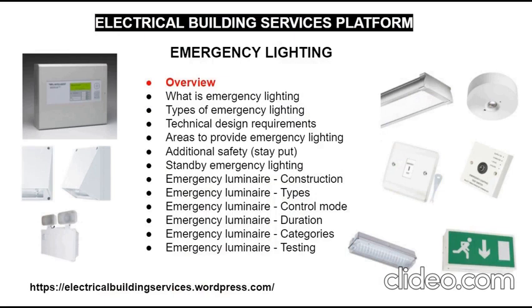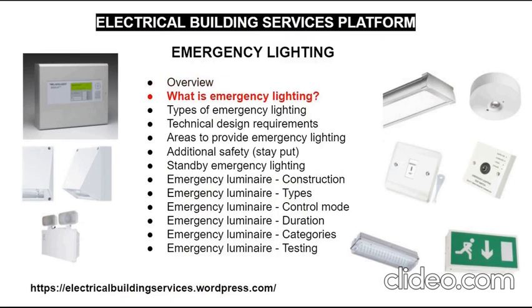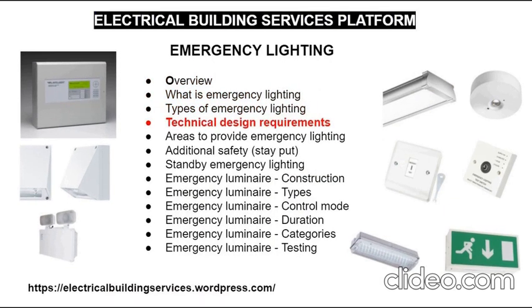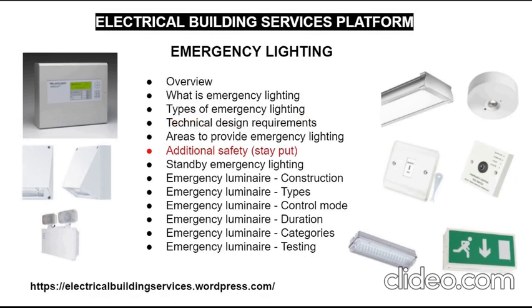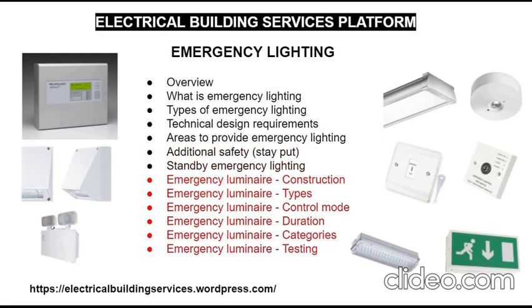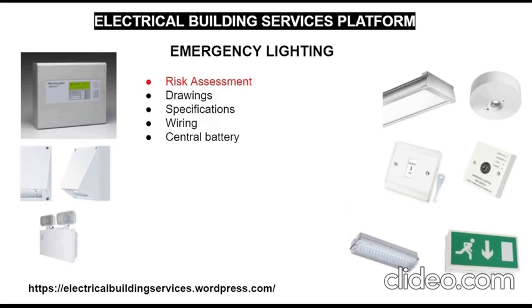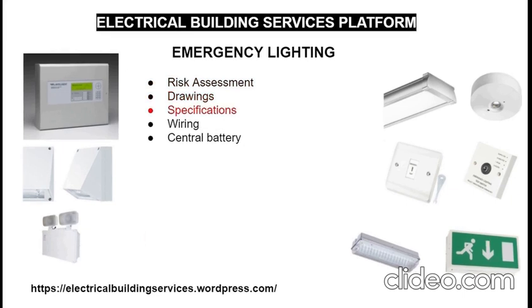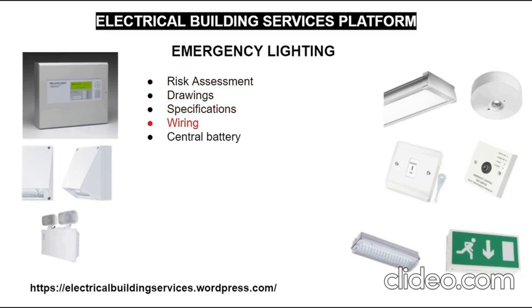There is still at least 1 hour of charge left. You can get the people to reoccupy the building, and the battery will now be charged fully again. But if, for instance, there is a building that requires 1 hour, and you put a 1 hour duration system in the building, then the building cannot be reoccupied until the battery is fully charged. It can take up to 24 hours.